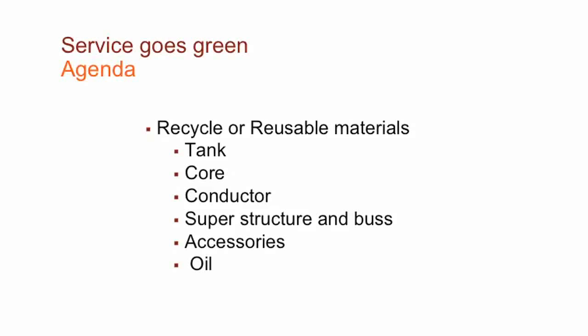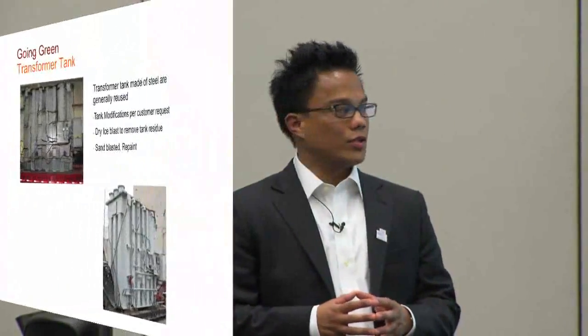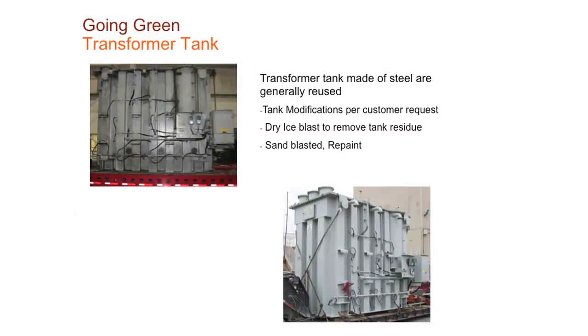The only other option is if we decide not to reuse the tank. The only way that it's not reusable is if there's a major rip or something like that. And usually these transformers can be welded back together, but typically if there's a major explosion, then we can't reuse the tank. But in most cases, we are able to reuse a tank. Also, our team in St. Louis and the other facilities as well has the ability to perform any tank modifications in case there are modifications that the customer requires before coming back to the facility.